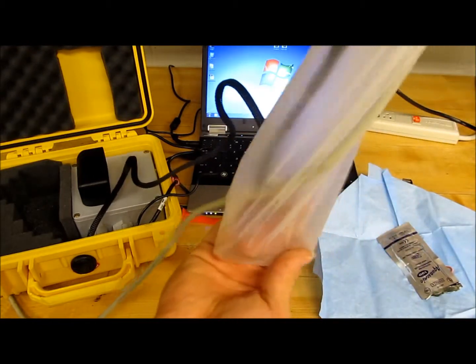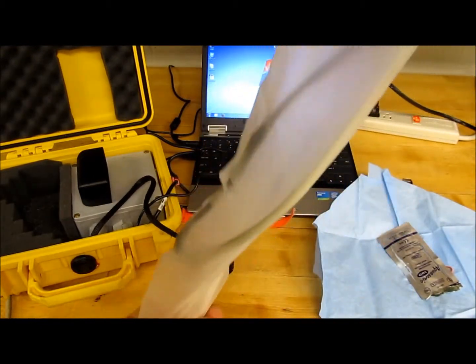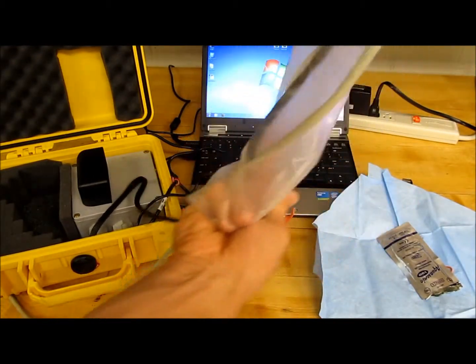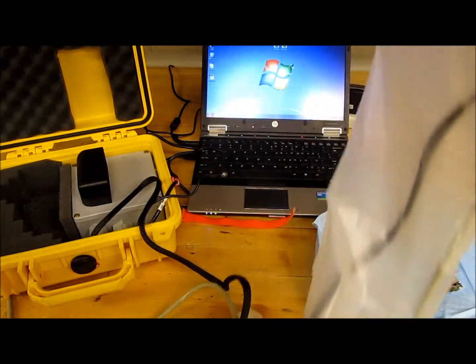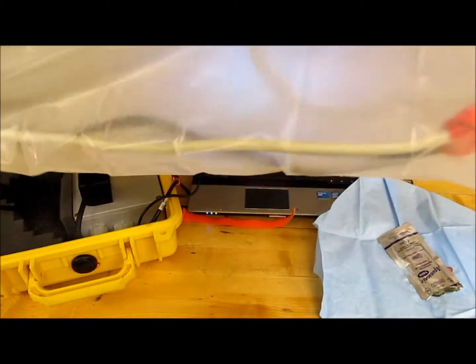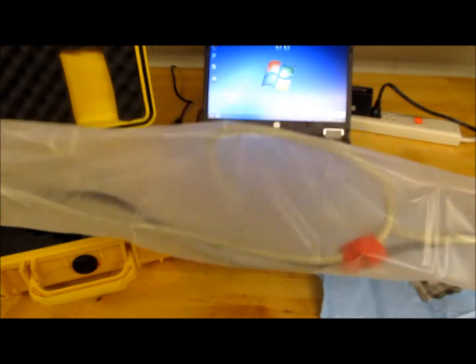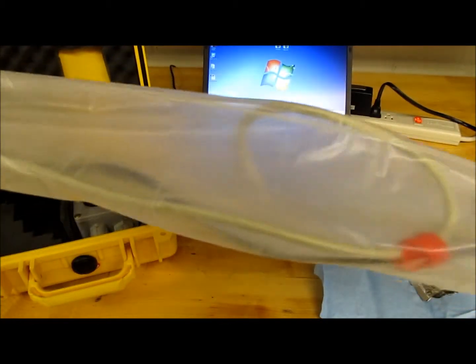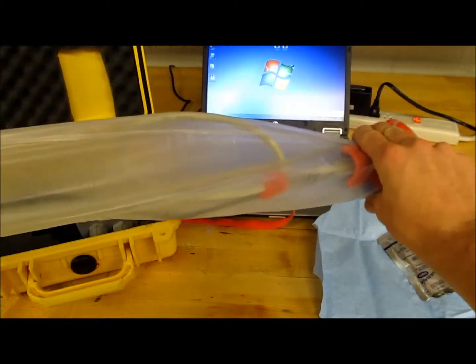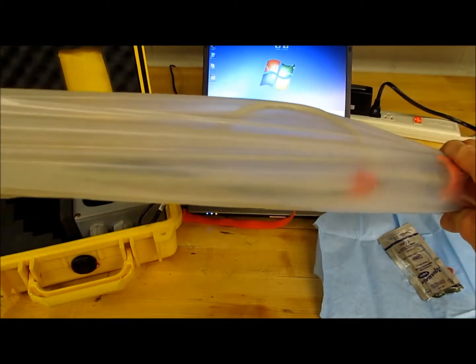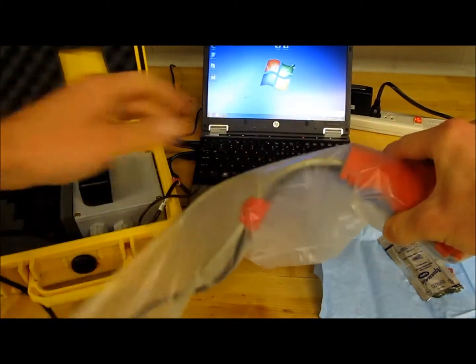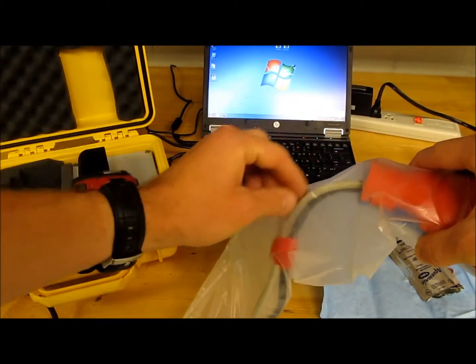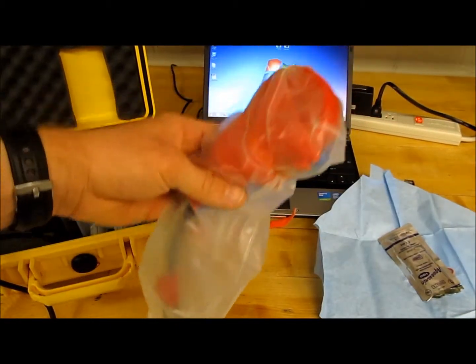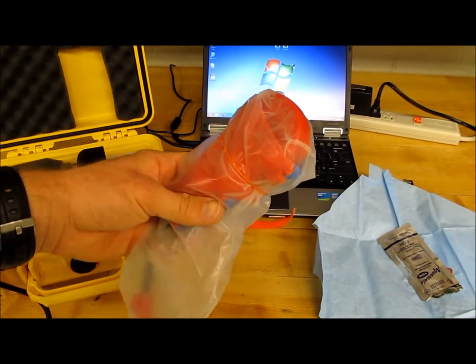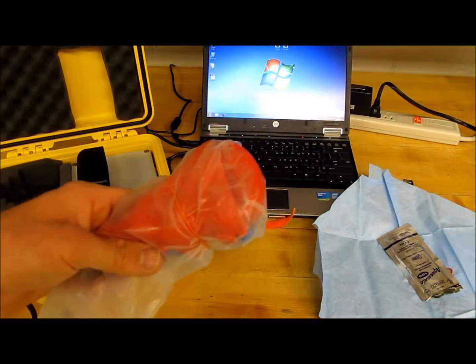Then we go ahead and pull the bag as far as we can so we can ensure that the cable doesn't get covered in ultrasound gel. So you'll note here that the loop that we created earlier is completely enclosed within the bag. So once again, any tension that's applied to this cable right here, we want it to go through the black cable and not through the actual ultrasound cable. So now you're ready to open up the program and start running the exam.